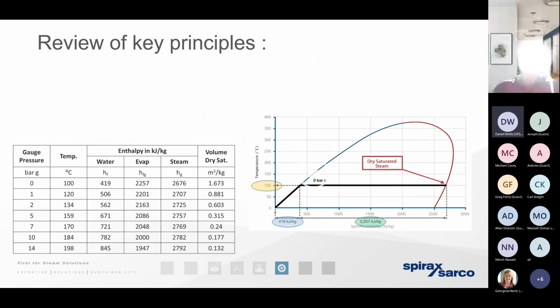Well, down in the bottom left-hand side of the screen, we've got the steam tables. There's a lot of very powerful information shown here on the steam tables. If we're moving away from the left-hand side of the screen, the first two columns demonstrate the pressure-temperature relationship that steam has that other sources of energy, such as low temperature hot water, simply don't have.